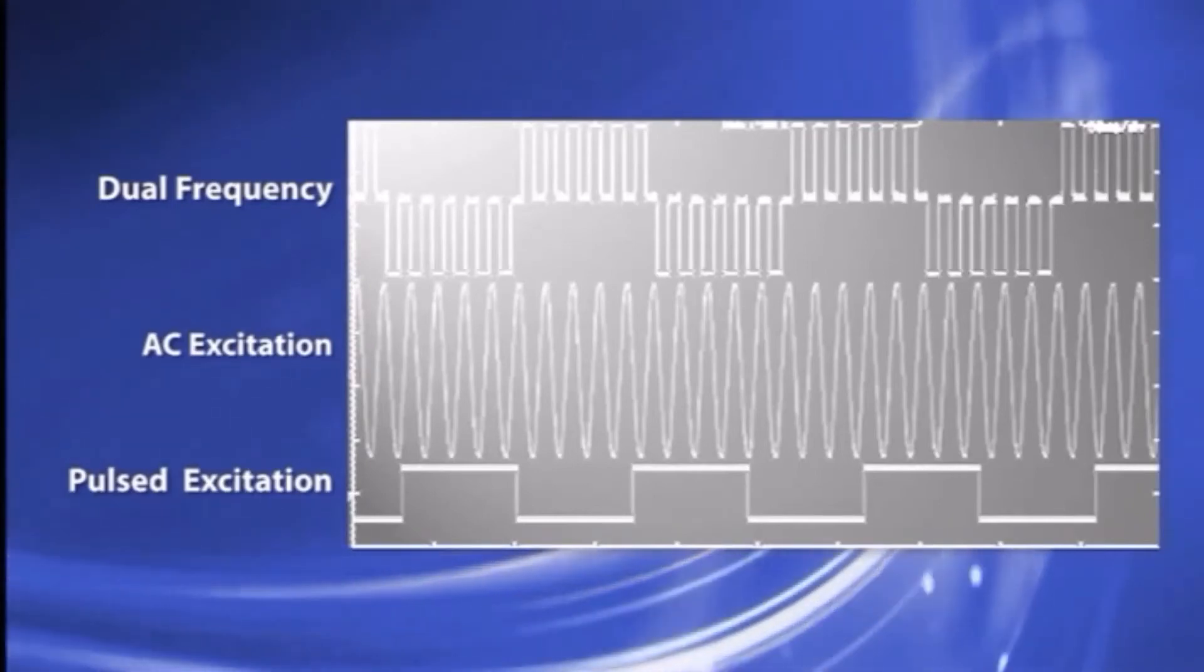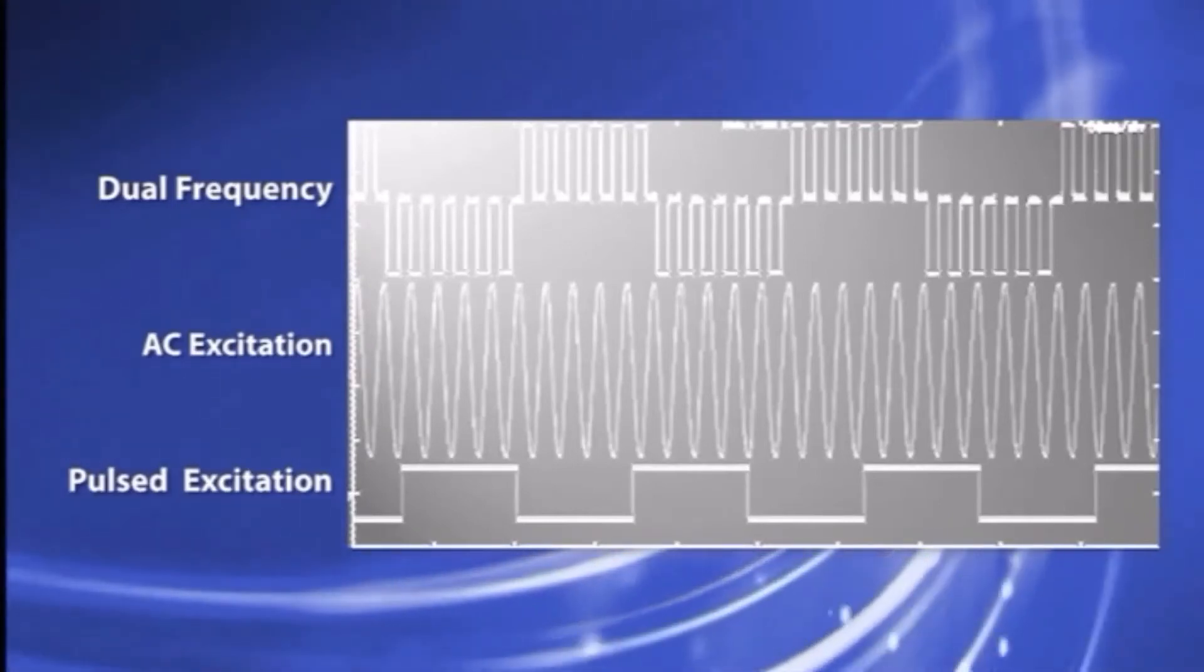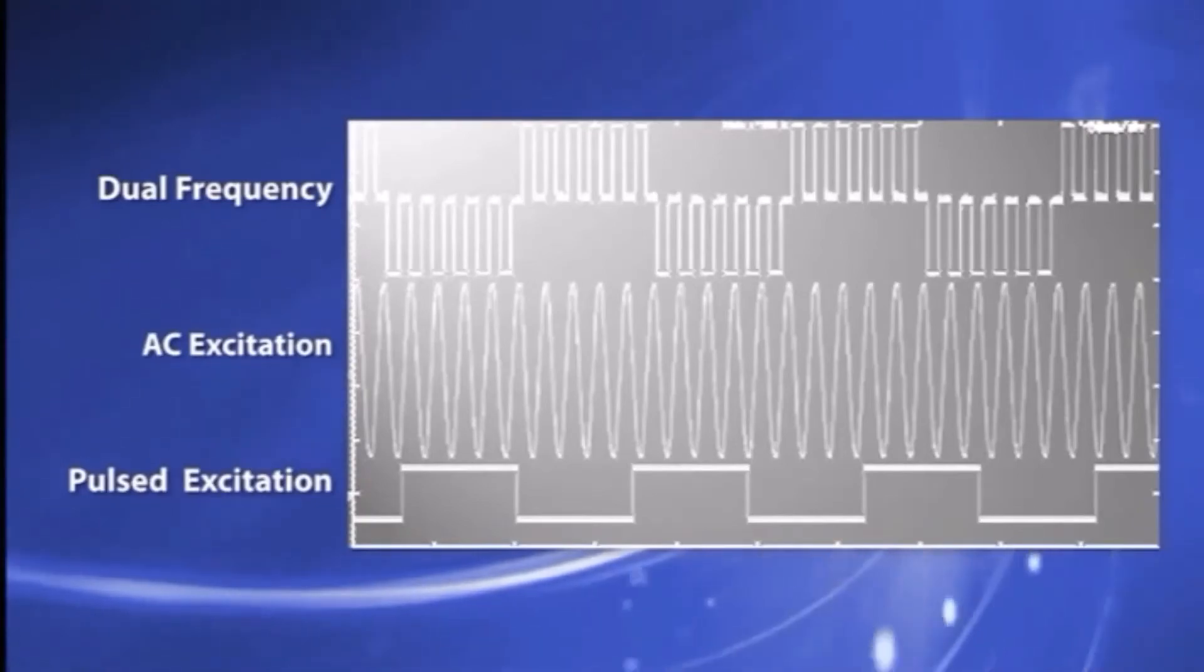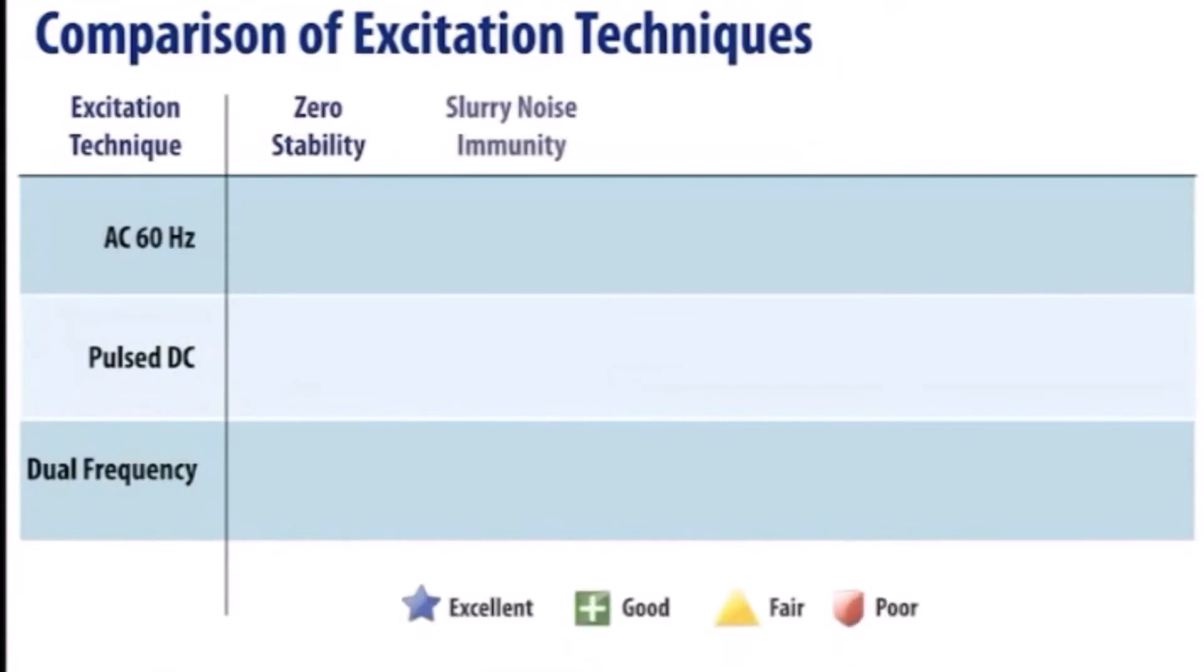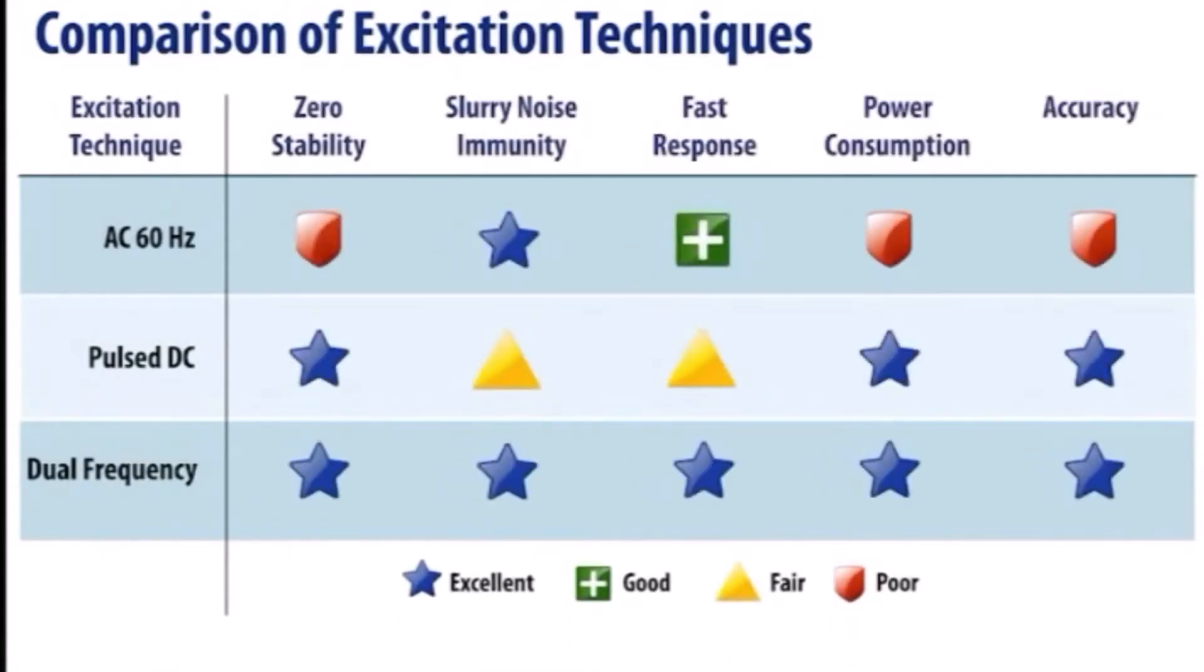Dual frequency excitation is an innovative method that superimposes high frequencies on low frequencies and utilizes the advantages of each while eliminating the previously discussed disadvantages. The combination of these methods results in the flow noise immunity and fast response of the high frequency excitation method and the high zero stability of the low frequency excitation method simultaneously.